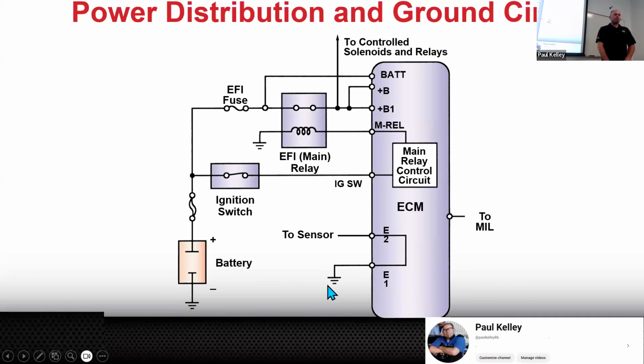If you were to check voltage drop with your black lead on the most negative and your red lead closer to positive, which sounds crazy because it's not positive, but it is, you shouldn't be dropping more than 0.2 volts right here. If you're dropping like 0.7 volts, there's something wrong with that ground.